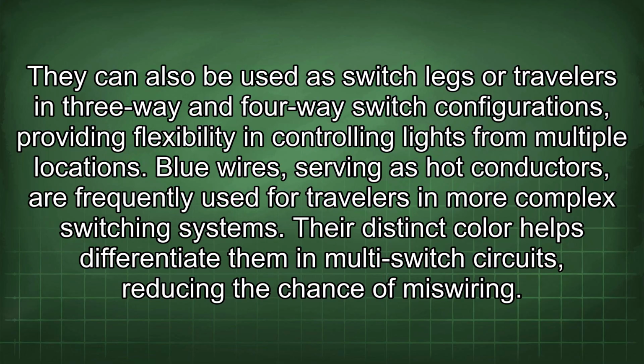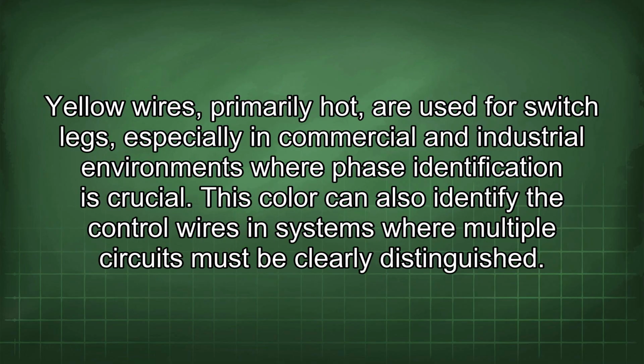Blue wires, serving as hot conductors, are frequently used for travelers in more complex switching systems. Their distinct color helps differentiate them in multi-switch circuits, reducing the chance of miswiring. Yellow wires, primarily hot, are used for switch legs, especially in commercial and industrial environments where phase identification is crucial. This color can also identify the control wires in systems where multiple circuits must be clearly distinguished.